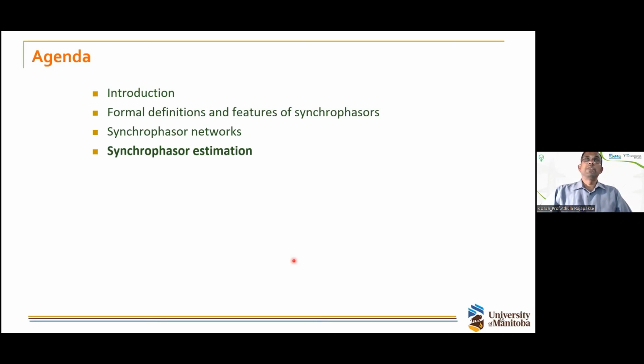Oh. If you are getting the sample values, you don't have to resample inside the PMU because you are directly getting the samples, but you may have to downsample, because, for example, a merging unit would send like 80 samples per cycle, which is probably too much for synchrophasor estimation. So you can probably do some sort of downsampling over there.